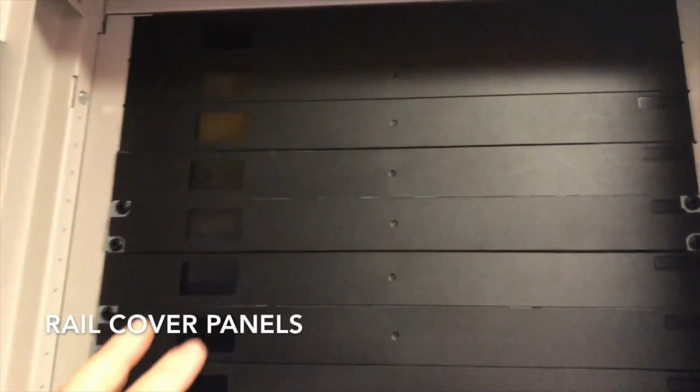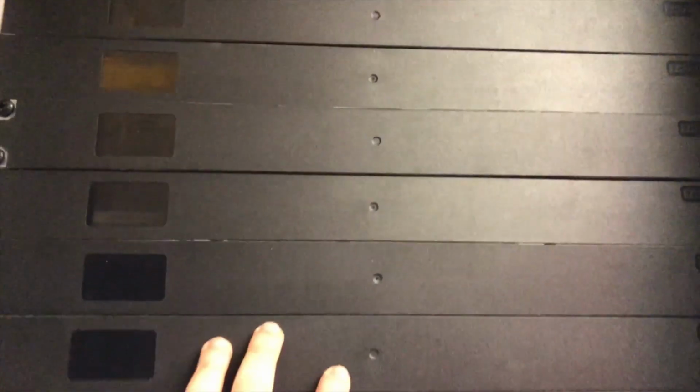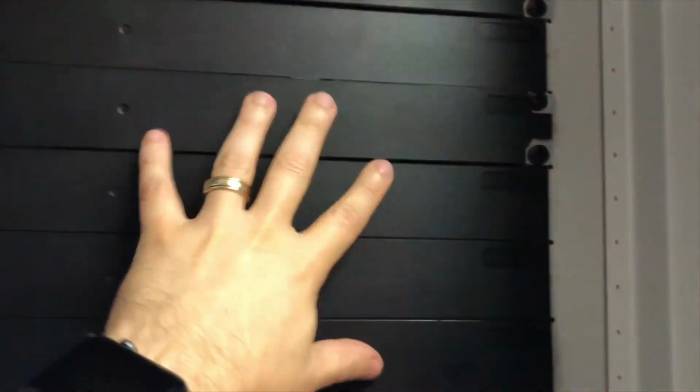Now, certain cabinets will have plates set up like this. What this is for, essentially, is airflow. So in these cases, there's nothing racked in these particular rails, okay? So instead of leaving them open, you put a cover on it. It actually allows you airflow in terms of hot, cold, etc. And they're easily removable just by popping them out. You can cut them to size and you can just place them back in there. Not every data center will have these, not every comms cabinet will have these or even need these, but it's always good to have it if you are concerned about things like power usage and how the air flows through your equipment. So there is my basic overview.